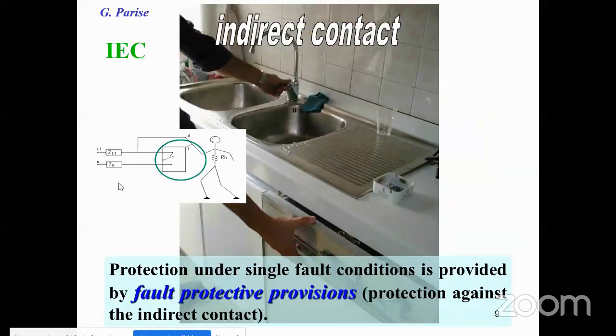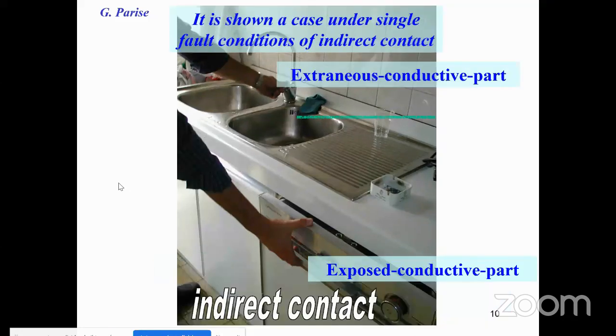Indirect contact is permitted only in condition of fault. A touch voltage is admissible obviously only in fault condition. So indirect contact in the IEC standard approach is discussed as protection under single fault conditions, which is provided by fault protective provisions. Let me show a case of indirect contact under single fault conditions. The figure shows a person in contact between a dishwasher and an extraneous conductive part, which is a water pipe.